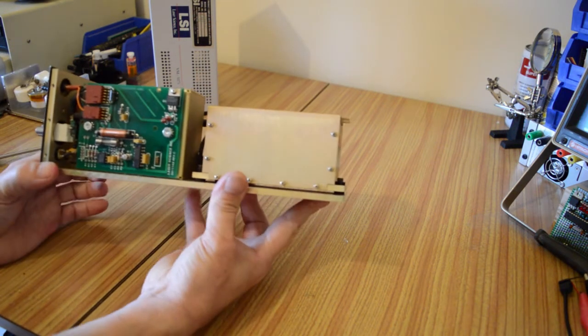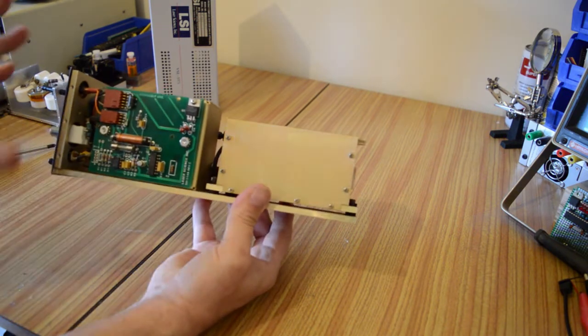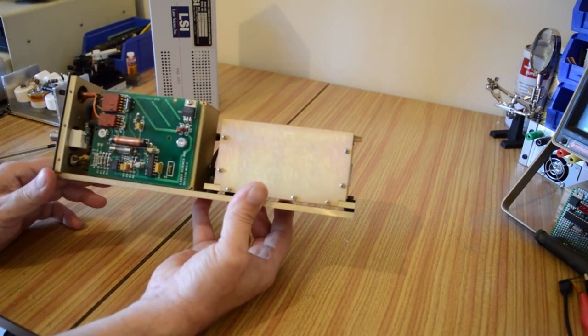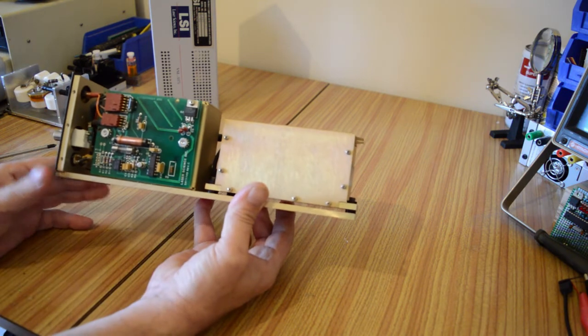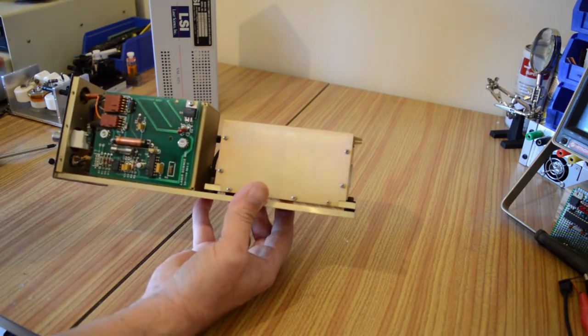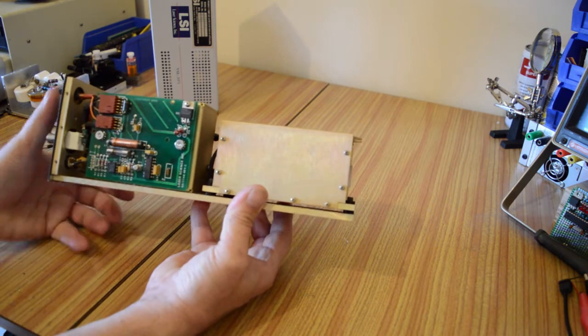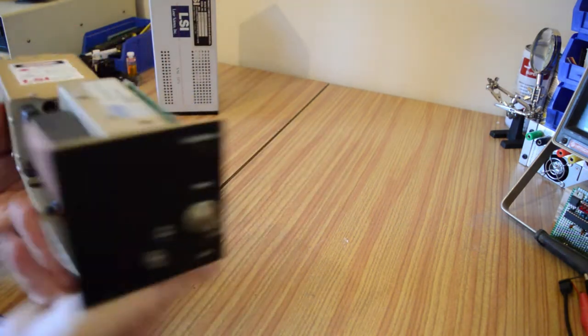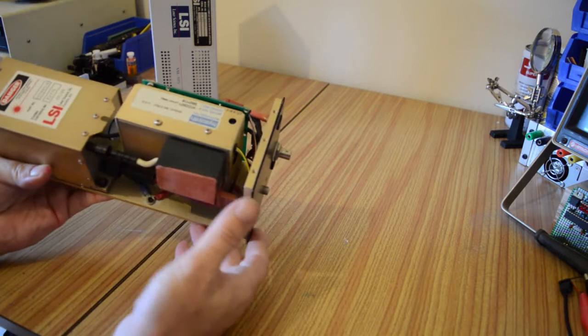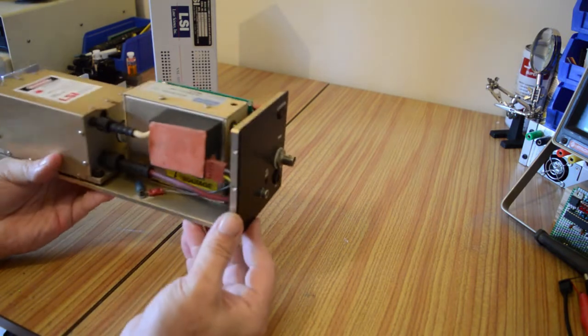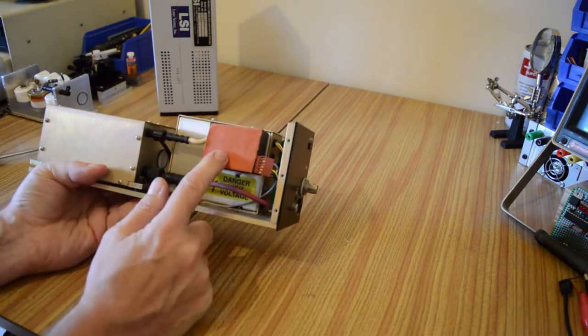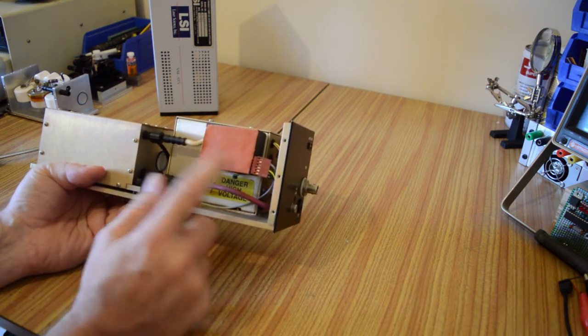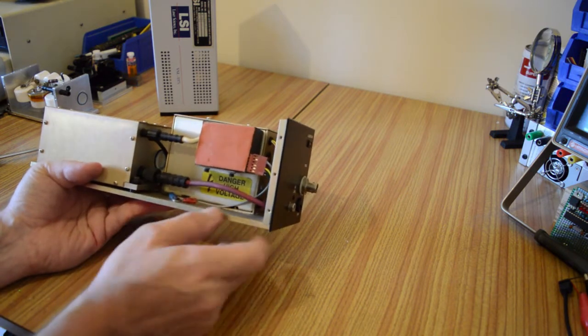We've got one PCB that we can see which is responsible for distributing power and dealing with the input pulses. There's an opto-isolator on the board here. When we receive a trigger signal in, that fires the trigger module and fires the spark gap. If we turn it around, on the other side we've got the high voltage module itself. Again it's potted in a nice little box, and with another unit here which contains the trigger transformer that triggers the spark gap, all full of silicone.